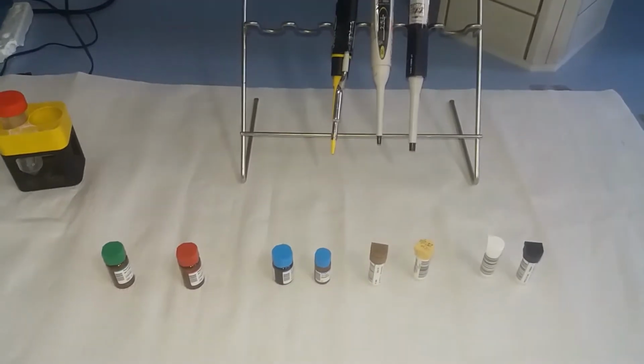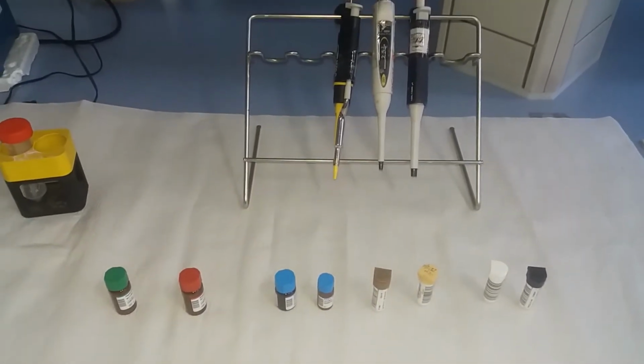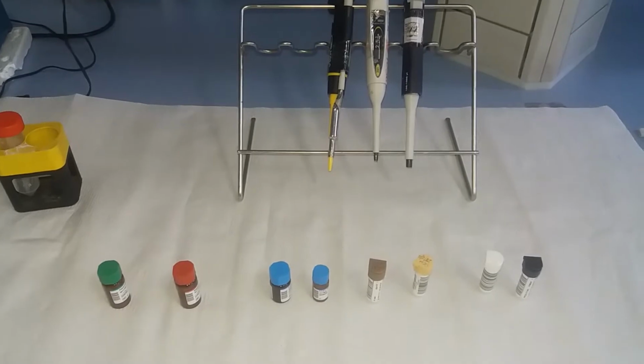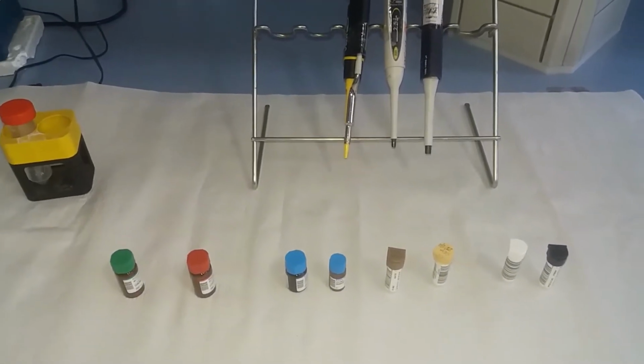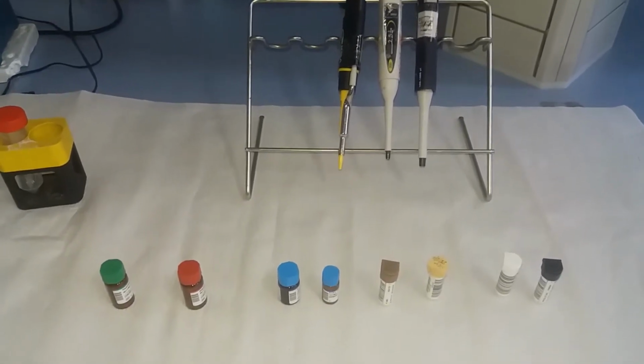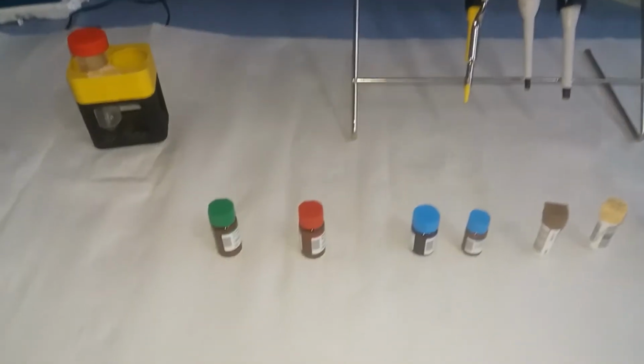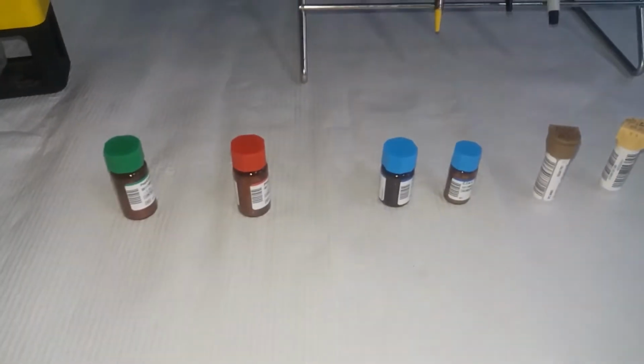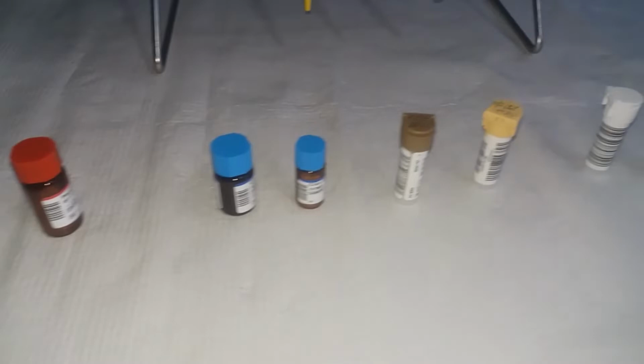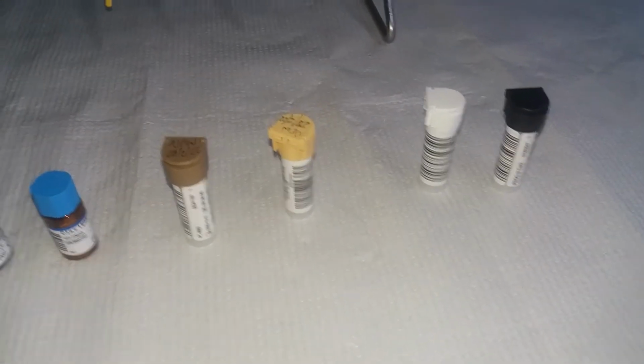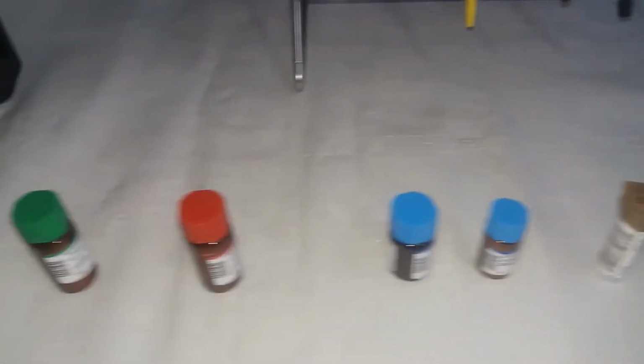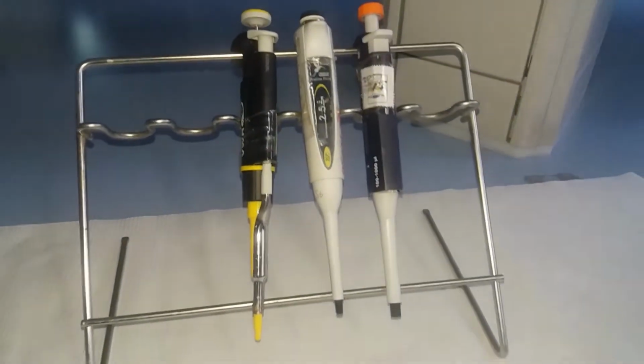Calibration frequency: calibration is done with every new cassette or lot change, as per the stability of the reagent, and after preventive maintenance. When QC is out of range, calibration can be performed. Quality control frequency: quality control can be performed daily, and may be performed after calibration.